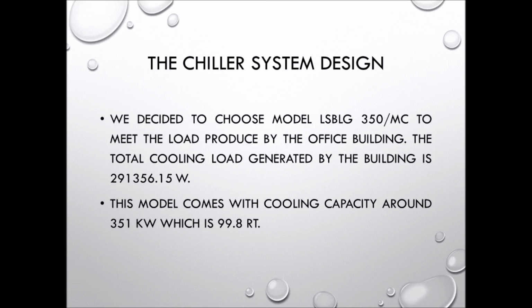For the chiller system designed for this office building, we decided to choose the model LSBLG 350MC to meet the load produced by the office building. The total cooling load generated by the building is 291,356 watt. This model comes with a cooling capacity of around 351 kilowatt, which is about 99.8 refrigerant ton.